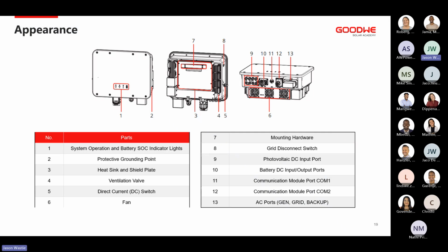Yeah. And then these are the parts and port numbers for the inverters for the ES Unique. We've obviously got the system operation battery SOC lights, protective grounding port, the heatsink and shield plate, ventilation valve, the direct current DC switch, and then the fans. So just to mention something about the fans, they are quiet, smart temperature controlled fans, so they don't constantly run. They're only set to turn on once your inverter reaches around 60 degrees Celsius, which would only really be under high loads or heavy PV intake. And that will run until the inverter reaches around 50 degrees Celsius, and then they'll turn off again. So they still have got the convection keeping it cool, as well as the forced convection with the fans.